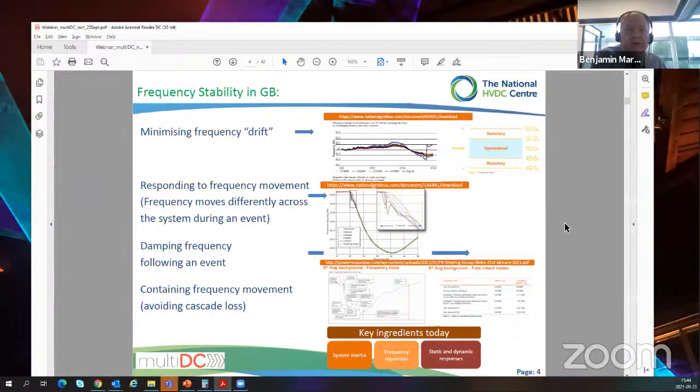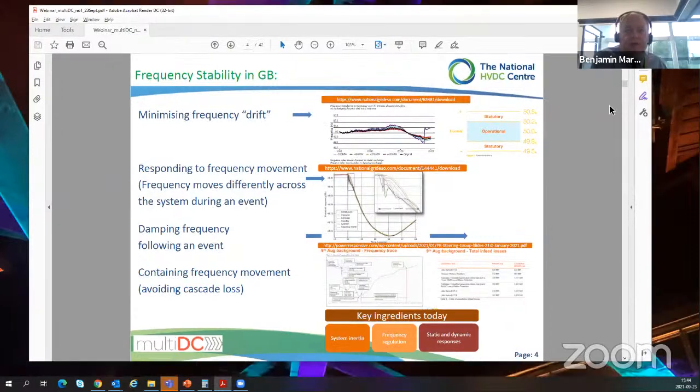And we also have a requirement, therefore, to damp an event, which requires us with the SQSS to achieve a 12-second angular oscillation damping. So 12-second time constant, that is. So effectively bring a reduction of quarter amplitude within 20 or so seconds.